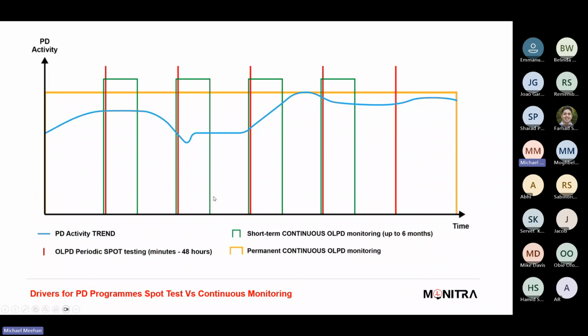Continuous monitoring on critical assets like generators, or at least frequent testing, is of value because you can start to look at operating current, temperature, load, and you can start to see PD at certain frequencies, at certain times, at certain loads, at certain temperatures. You might have a normal frequency PD at that temperature, and you think, right, that's normal. And every time you get that temperature, the PD is similar, and it'll reduce at other temperatures, and then all of a sudden you've got what healthy looks like for that machine. So that's the real benefit of having that continuous monitoring, and you can start to then look at real changes based on correlations to temperature and other parameters and get that extra sensitivity in your measurements, which gives you the ability to make sensible management decisions on interventions if you think you need to make interventions.